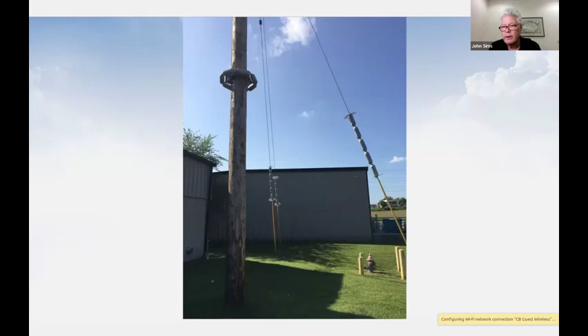When they put line guard on those guy wires, that stopped that path. They also put pole guard on the wooden pole. This was a situation that utility had problems with for probably four years in a row, every spring, and this solved the problem. They haven't had a problem since.